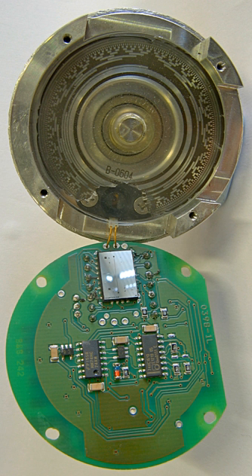A rotary encoder, also called a shaft encoder, is an electro-mechanical device that converts the angular position or motion of a shaft or axle to analog or digital output signals. There are two main types of rotary encoder, absolute and incremental. The output of an absolute encoder indicates the current shaft position, making it an angle transducer. The output of an incremental encoder provides information about the motion of the shaft, which typically is processed elsewhere into information such as position, speed and distance.